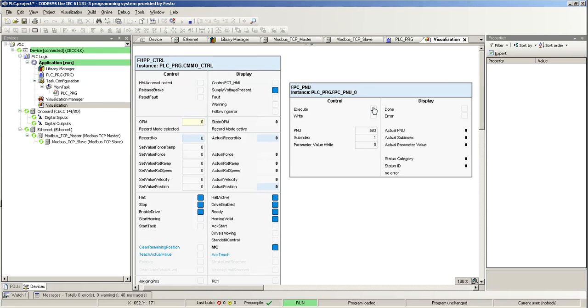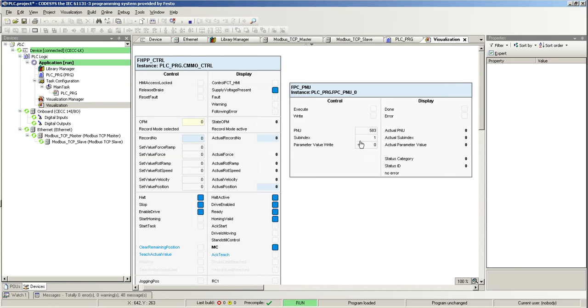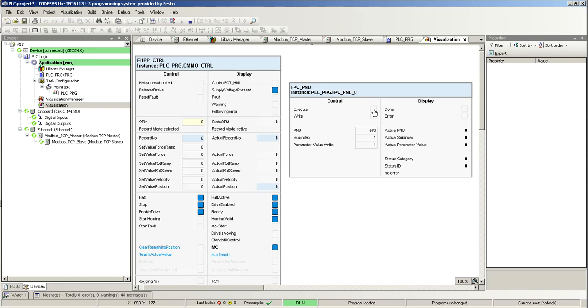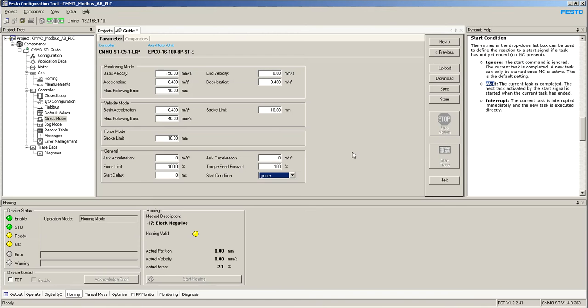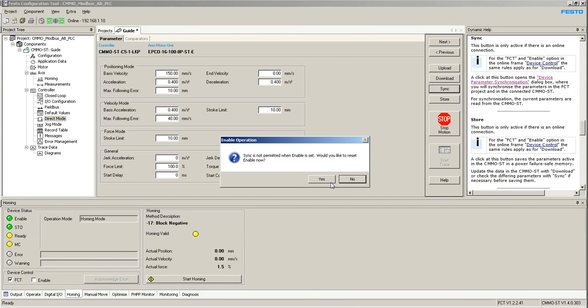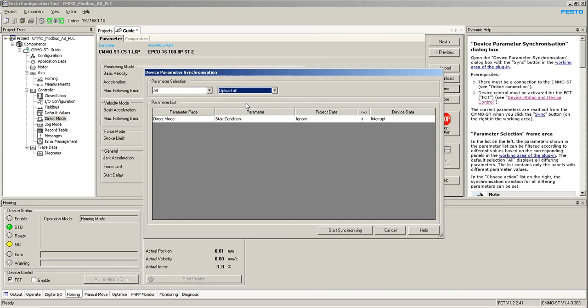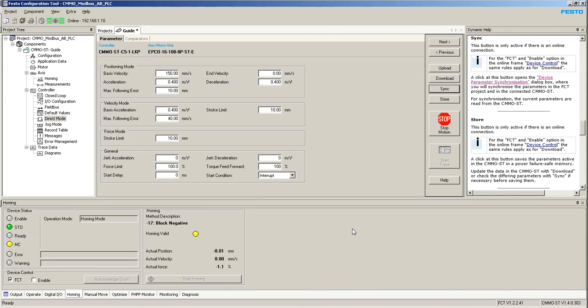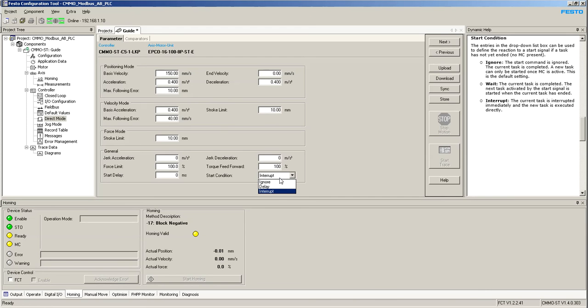What I'm going to do now is I want to set it to interrupt. I'm going to set it to 1 here. Now I make the write bit to true, and I execute. Execute, done. Now I read back again. Now it's set to 1. And I can confirm this going to FCT here. What I can do is sync to see if there are any differences between the device and the project. I should see a difference here. It says that the project, of course, the last change I did on the FCT on the project was ignore. But because of CODESYS, I changed that parameter. Now it says interrupt. Here what I could do is upload, start synchronizing, and then it changes to interrupt. I could do the same thing for the three options here, ignore, delay, interrupt, depending on the value here.